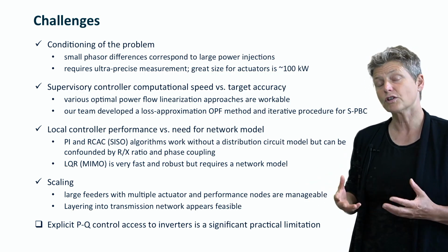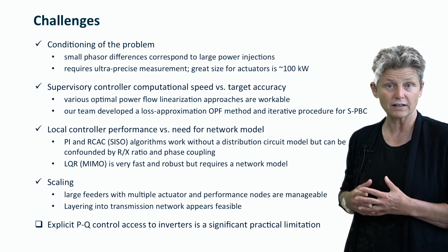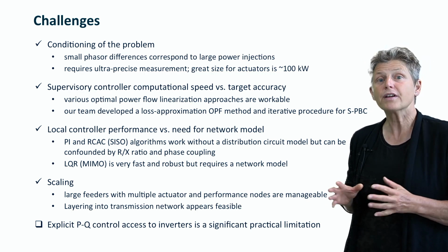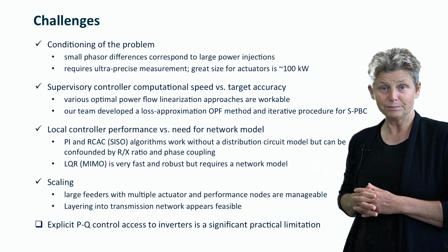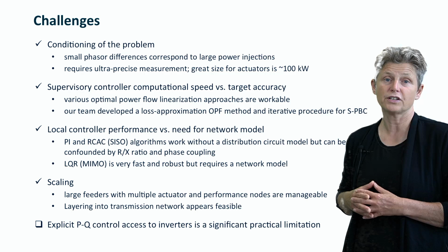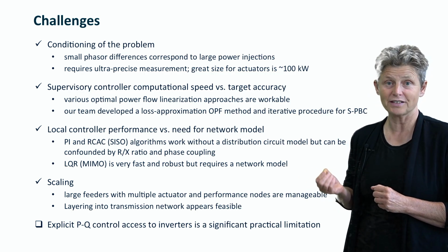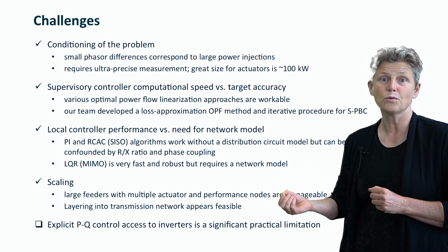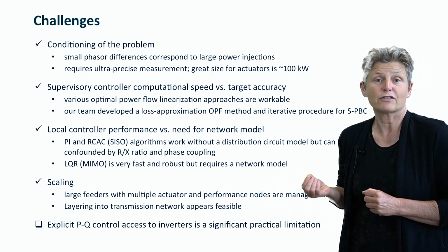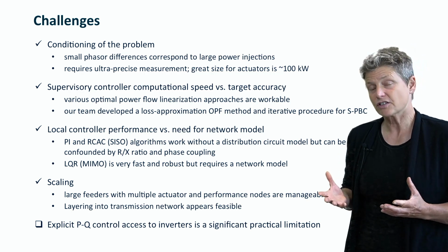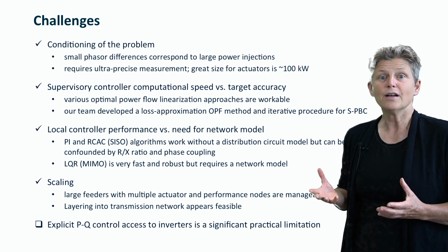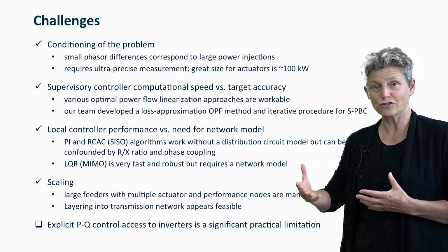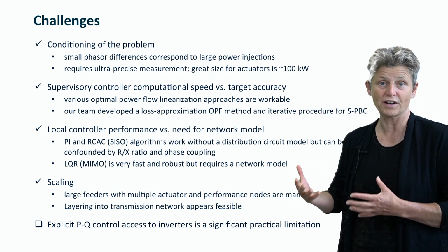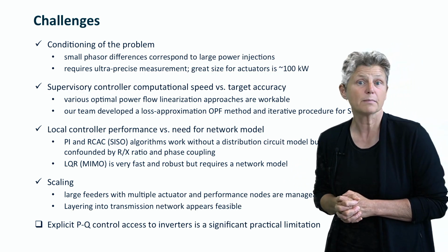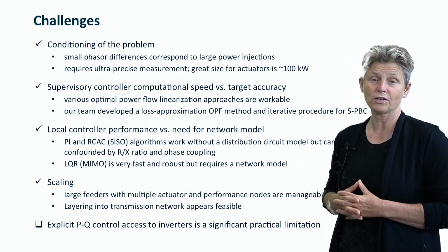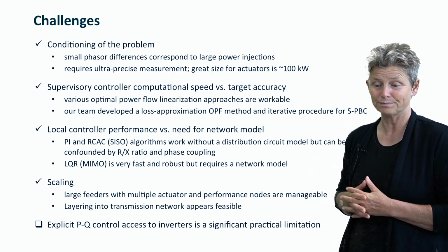It's more typical to have, say, real power control with a power factor setting or something sort of higher level. So that actually posed an issue for us just in terms of the time step, because we couldn't get inverters to respond to our signal as rapidly, on as short a time step as we might have liked. That's not a basic physics limitation. That's just a limitation of who has access to what level of control loop. And to me, it makes a lot of sense to just embed this whole phasor-based controller inside the inverter.